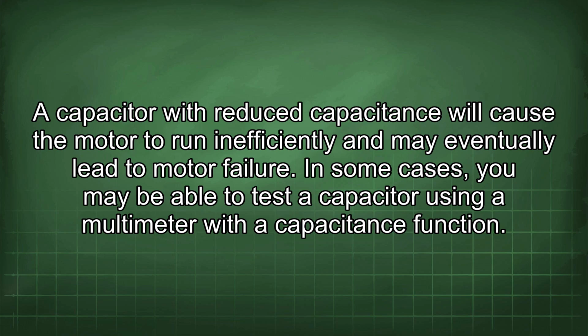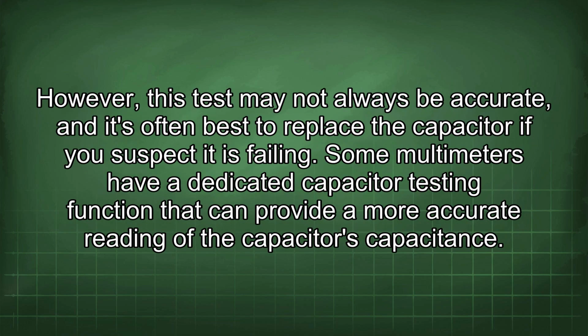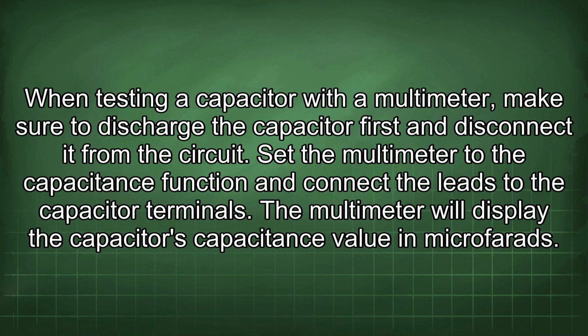In some cases, you may be able to test a capacitor using a multimeter with a capacitance function. However, this test may not always be accurate, and it's often best to replace the capacitor if you suspect it is failing. Some multimeters have a dedicated capacitor testing function that can provide a more accurate reading of the capacitor's capacitance. When testing a capacitor with a multimeter, make sure to discharge the capacitor first and disconnect it from the circuit.